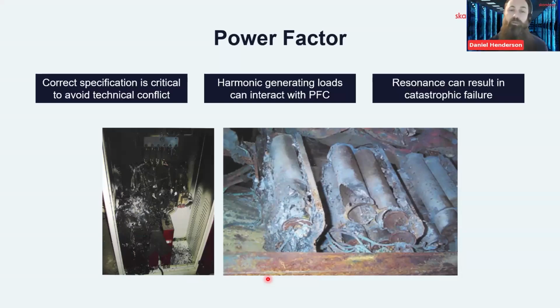I've seen 3 of these as well. 2 of them, it just resulted in the capacitor banks failing and then the equipment going offline. One ended up in a fire, which obviously isn't ideal from a safety perspective or a reliability perspective.